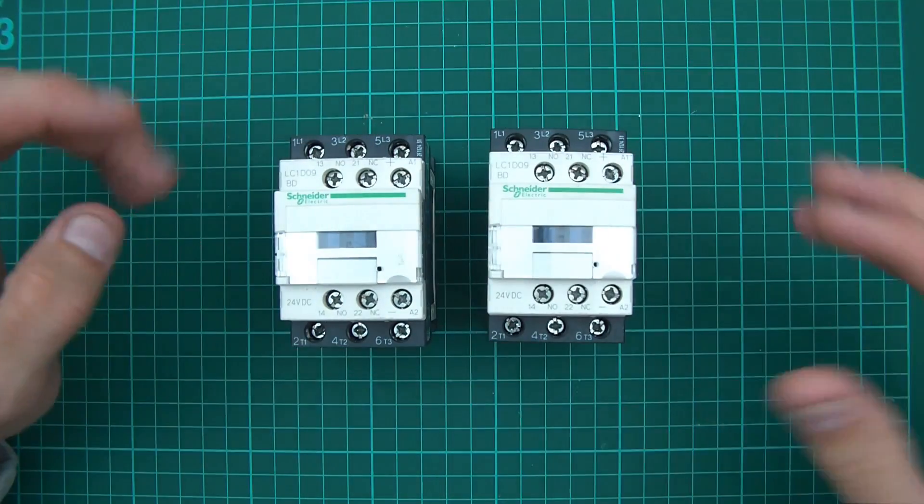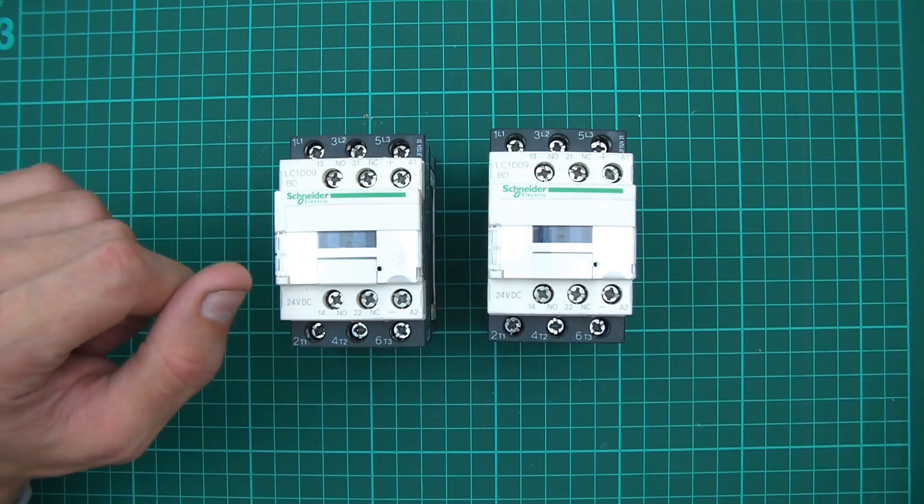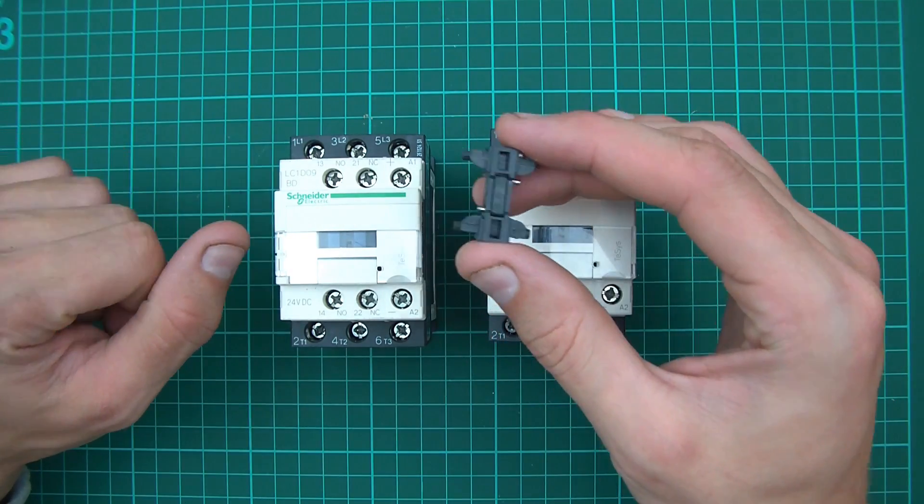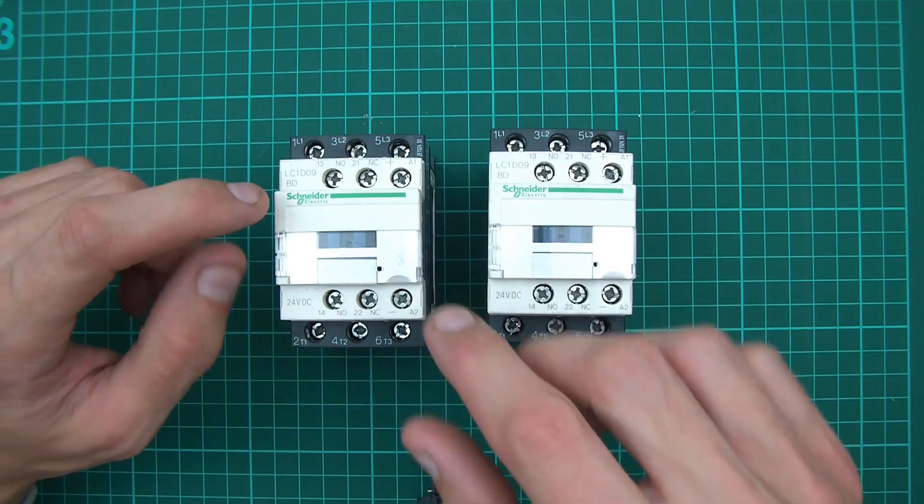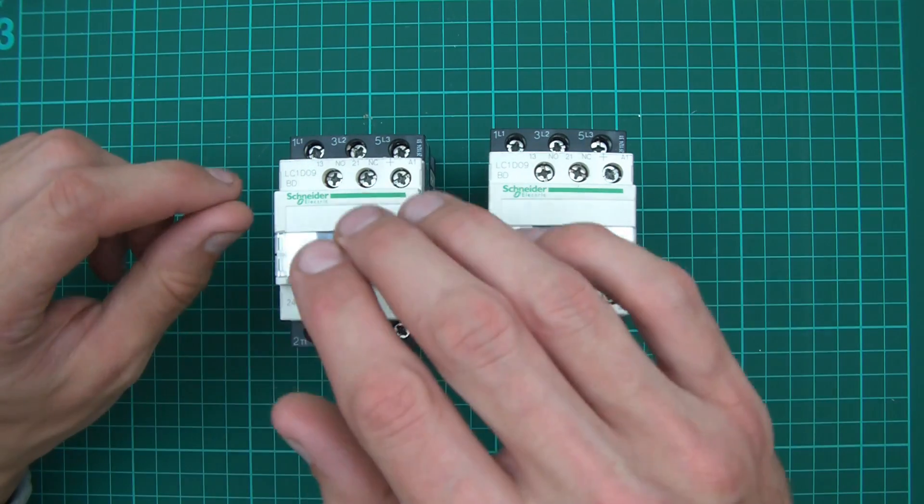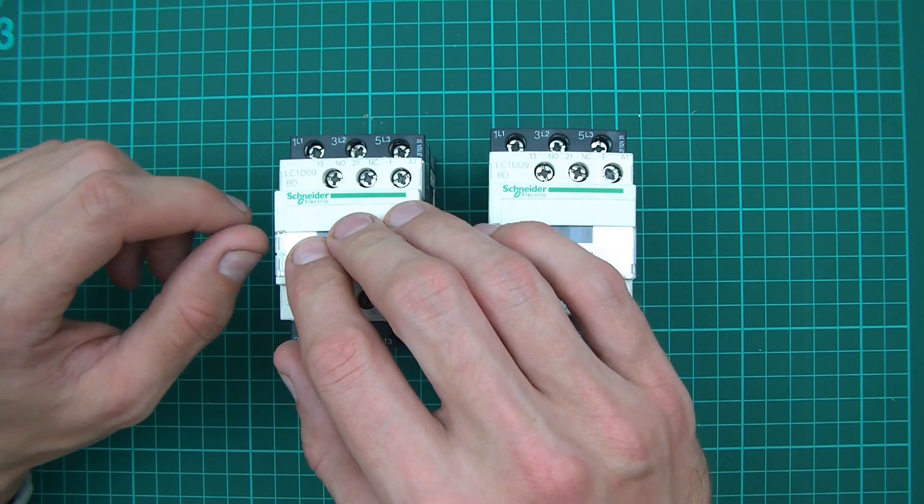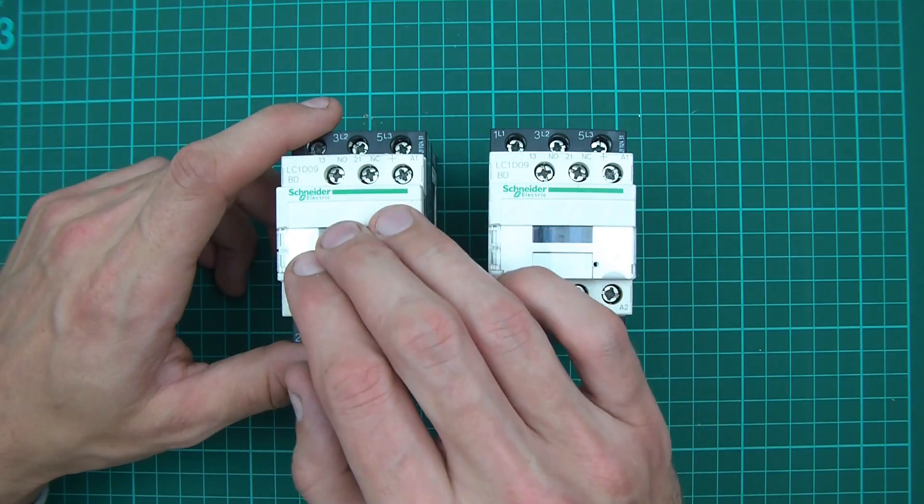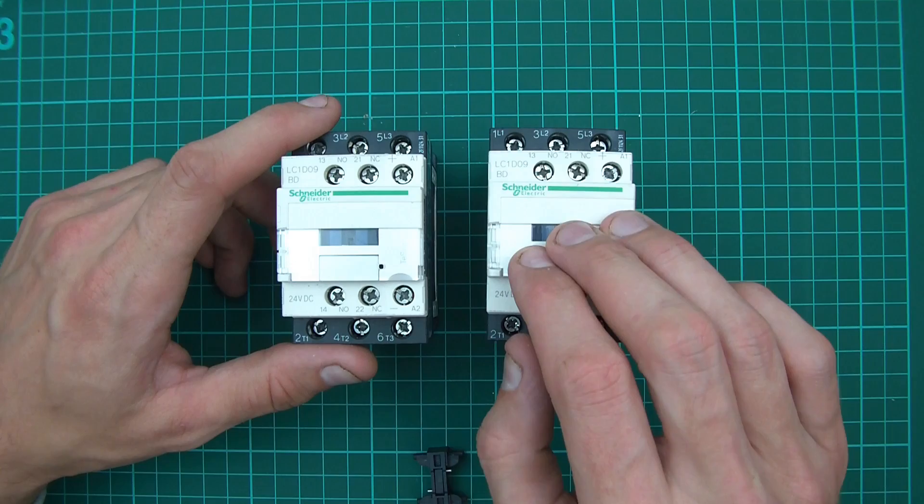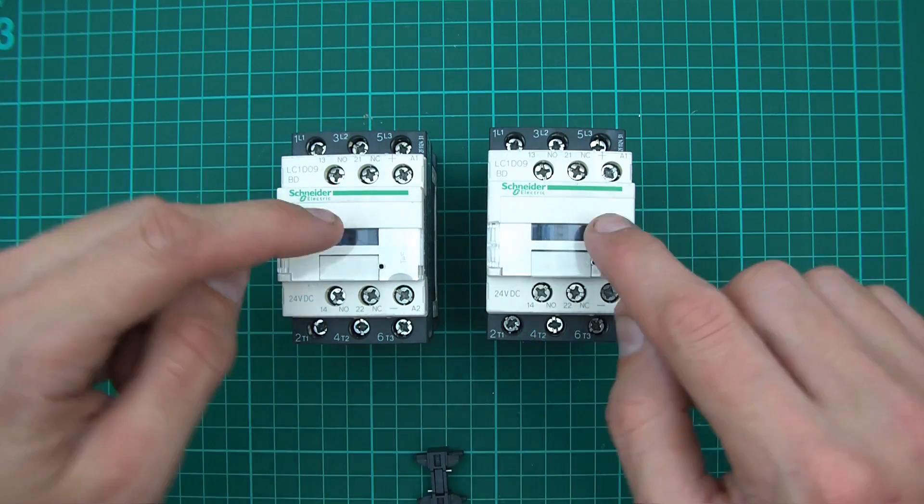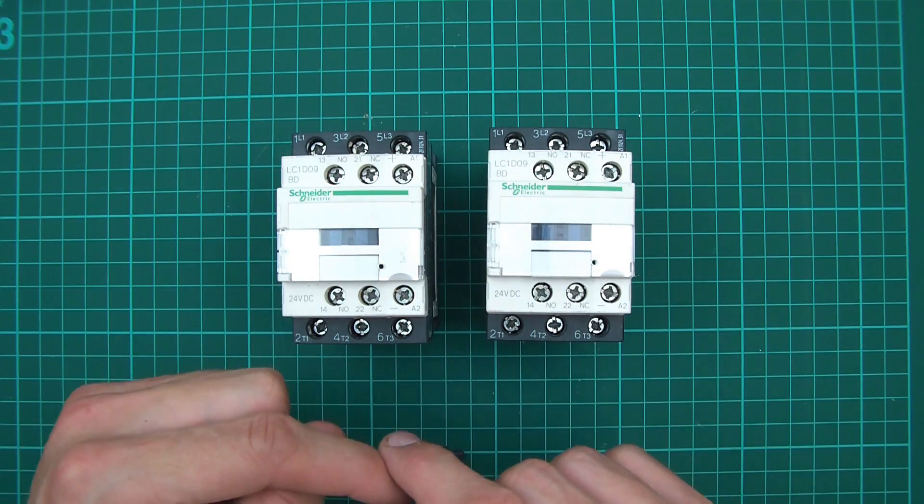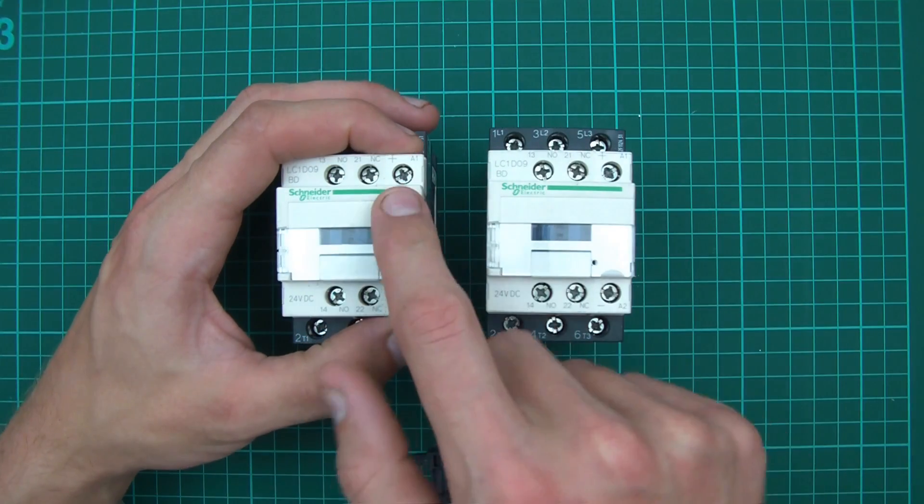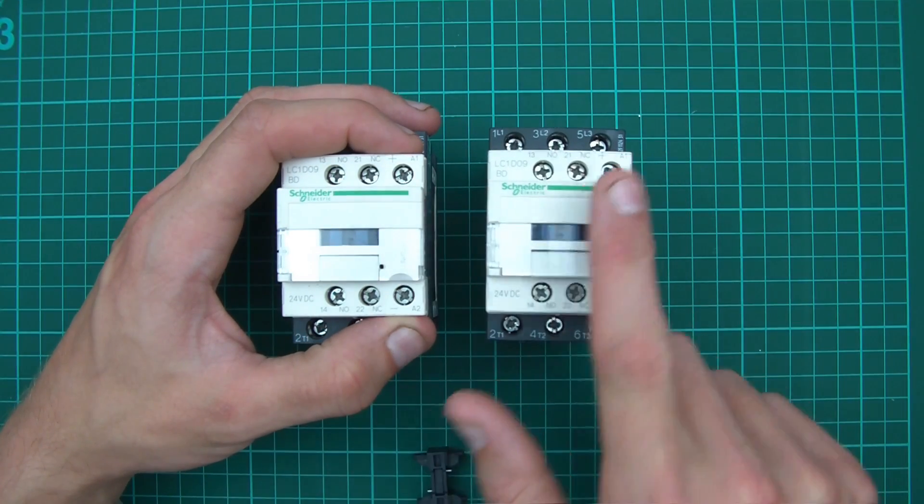I've got two contactors. The other thing I've got is this mechanical interlock, and the reason I've got this is because we've got live and neutral from solar and live and neutral from mains. We can't allow both of them to join at the same time.